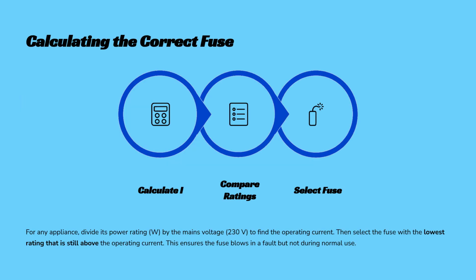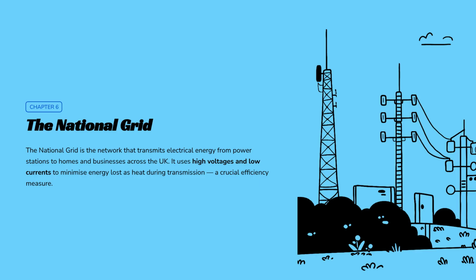To calculate the correct fuse for any appliance, divide its power rating by the 230-volt mains supply. Choose the fuse with the lowest standard rating that is just above that operating current to ensure it provides effective protection. Now, we will explore the national grid. This is the expansive network that transmits electrical energy from power stations to homes and businesses throughout the UK, using high voltages to minimize energy loss.